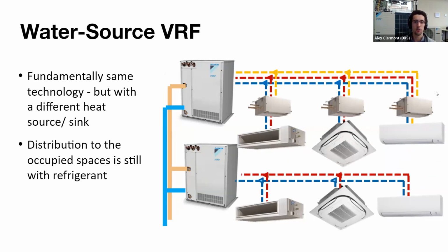So we talked about air source VRF, but now let's talk about water source VRF systems. Instead of rejecting or absorbing heat from the air, these can use water. They're available as heat pump or heat recovery, just like air source machines. Same distribution network as air source, but the main difference is the heat sink or heat source.